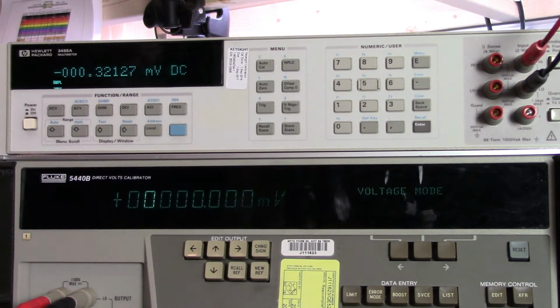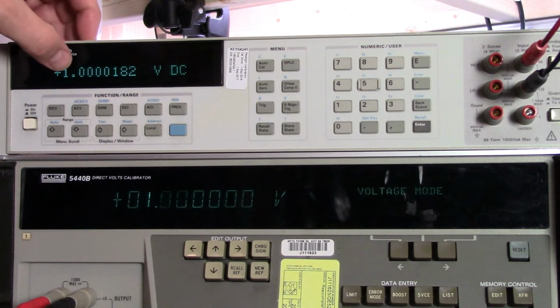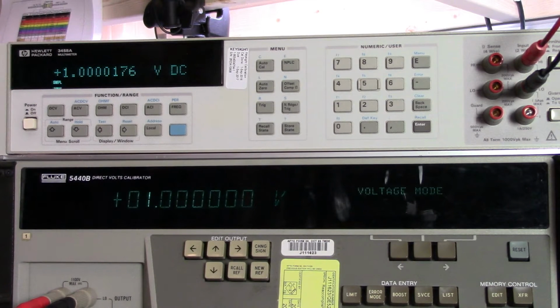So let's go in. We have it set for DC volts. Let's set 1 volt here, hit enter, and turn it on. And right out of the gate, you're looking at 1.0000 volts. That's pretty good for no calibration, no warm up, no nothing. Let's try 10 volts. You're looking at 10.000025. Again, not too bad. Let's try 100 volts.